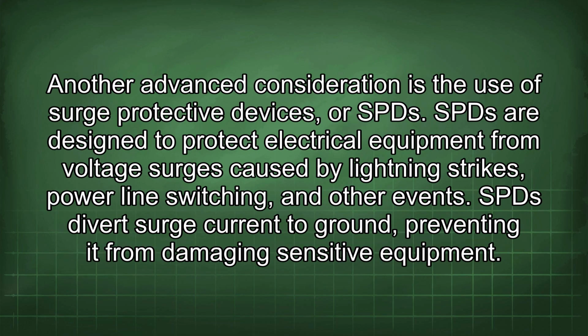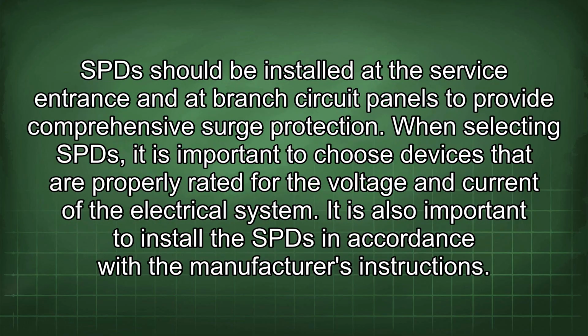Another advanced consideration is the use of surge protective devices, or SPDs. SPDs are designed to protect electrical equipment from voltage surges caused by lightning strikes, power line switching, and other events. SPDs divert surge current to ground, preventing it from damaging sensitive equipment. SPDs should be installed at the service entrance and at branch circuit panels to provide comprehensive surge protection. When selecting SPDs, it is important to choose devices that are properly rated for the voltage and current of the electrical system.